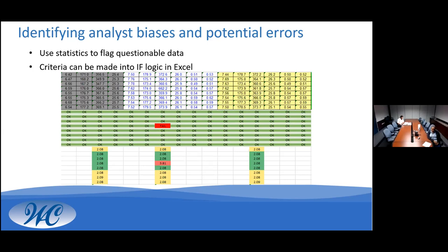Section 7.7.1 requires us to have a procedure for monitoring the validity of results and be recorded in a way that trends are detectable. Data recorded within Excel spreadsheets can be analyzed with simple if logic rather than diving into more complex coding. The example I'm showing here is the logic: if conductivity ratio is outside of specification, flag this cell bright red for review. So as soon as I paste the data into this template, it'll either flag it okay if it's good or red if it's bad, and I'll do further review from there. This data point shows a ratio of 3.81 while everything else is 2.08.